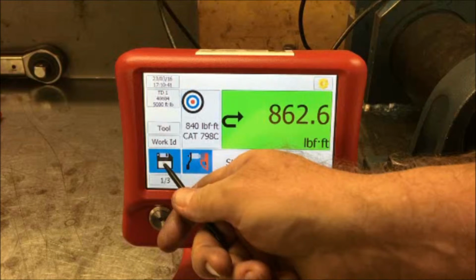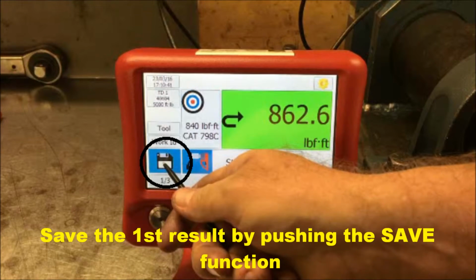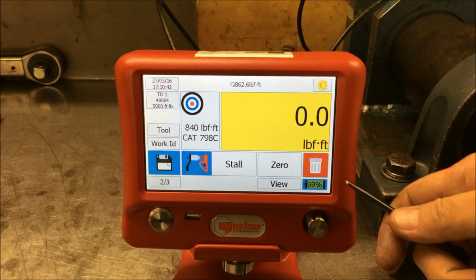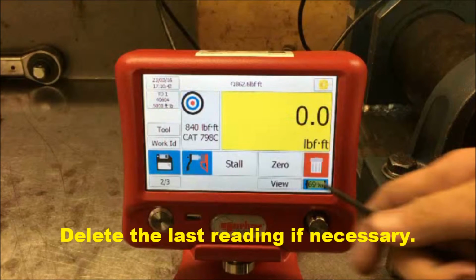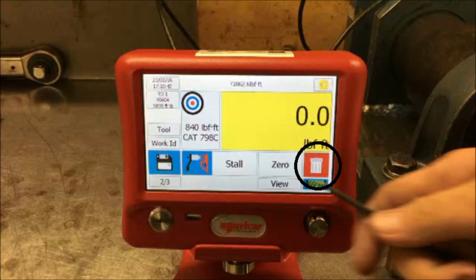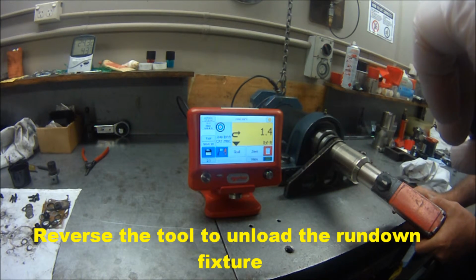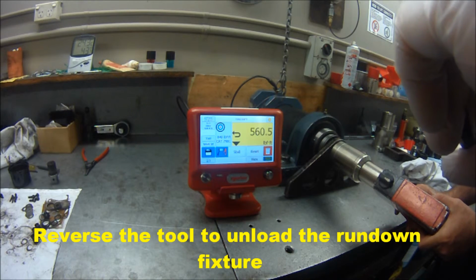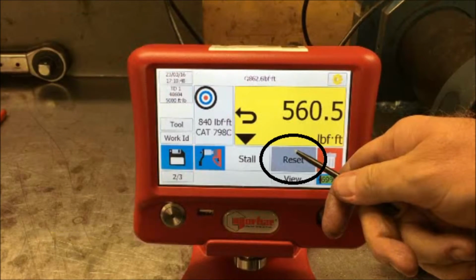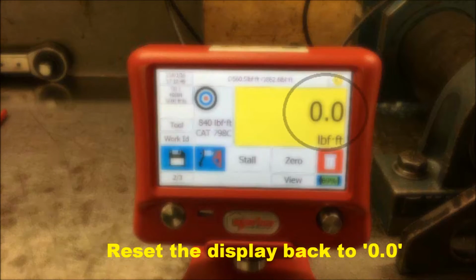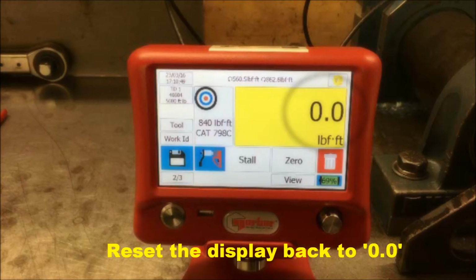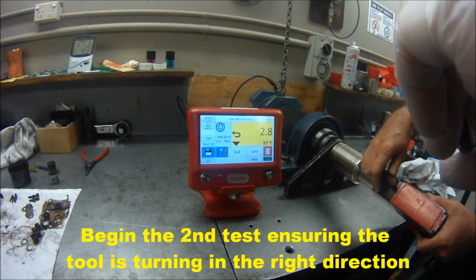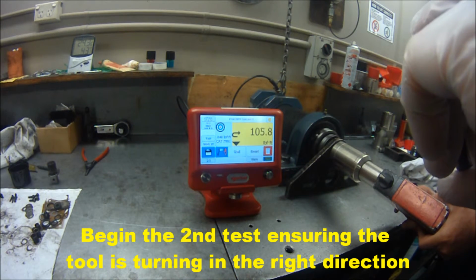If the tool stalls within the set variance, it will be displayed as green. You can then save the first result by pushing the Save Function button on the left hand side. If the target torque displayed on the screen is either too high or too low, and therefore outside the acceptable variance limit, that result can be deleted. Before beginning the second test, reverse the tool to unload the rundown fixture. Reset the display to 0. Make sure the tool is now operating in a clockwise direction to begin the second test.